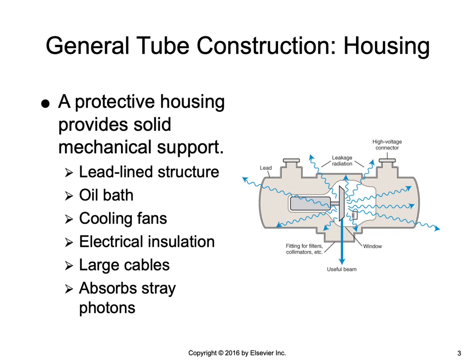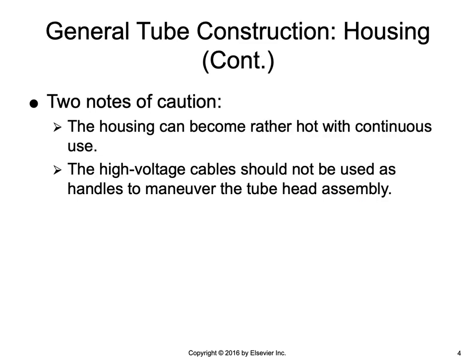The protective housing with the x-ray tube situated inside serves as an electrical insulator and a thermal cushion for the x-ray tube, in addition to being a protective device against physical damage. There are two notes of caution about the x-ray tube housing. Because it is on for a very extended amount of time, the housing can become very hot. This is most likely to occur with fluoroscopic units, and most permanently installed units have the tube located under the tabletop to limit the possibility of contact and prevent the RT or even the patient from getting burned.